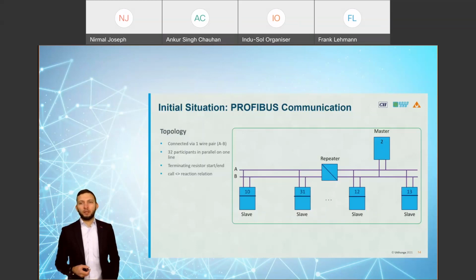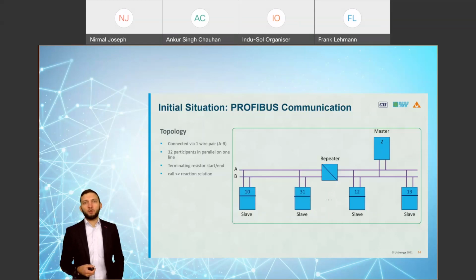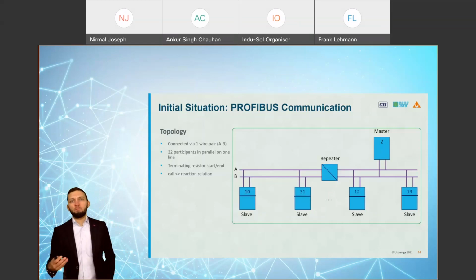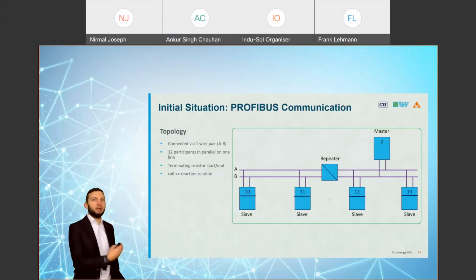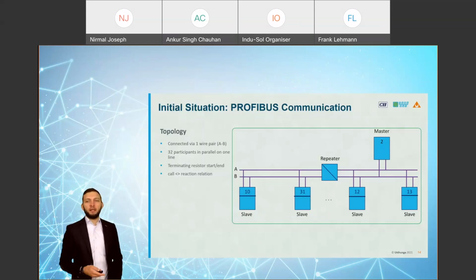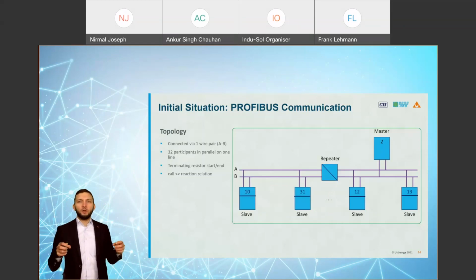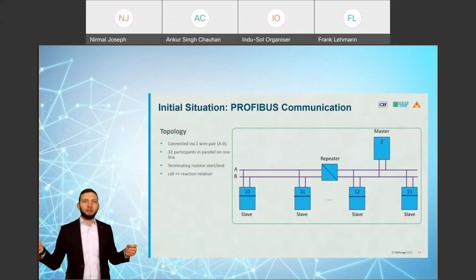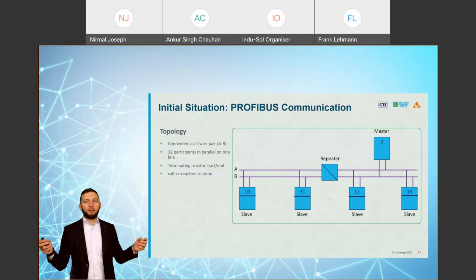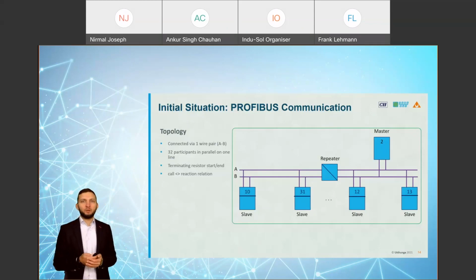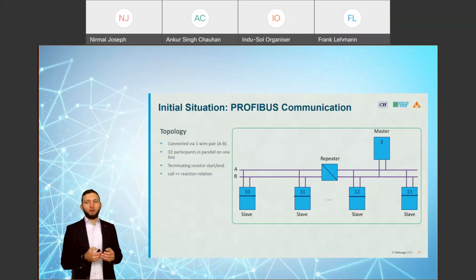In terms of topology, we can have up to 32 devices per segment. If I need more devices or a longer line length, I have to use repeaters, which repeat the frame into the other segment and so on. I also have to set a termination at the end and starting point of each segment. This is the communication and topology in the PROFIBUS network.